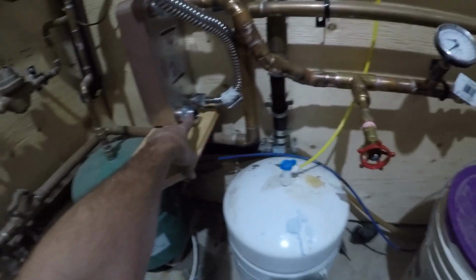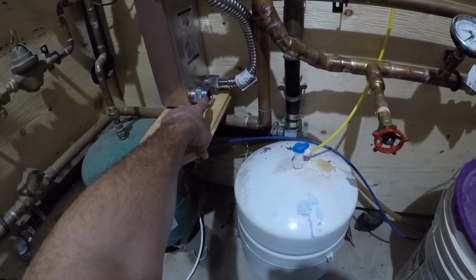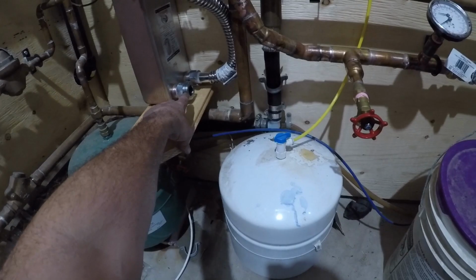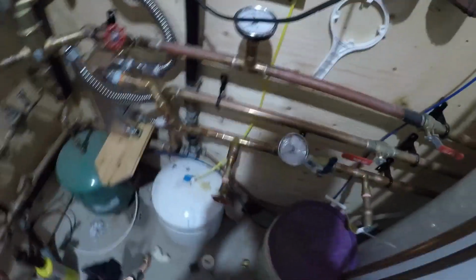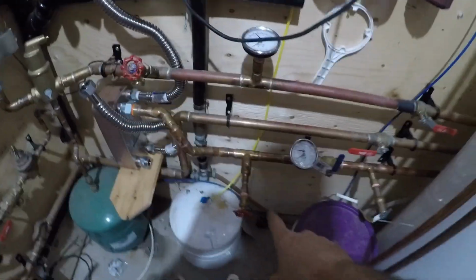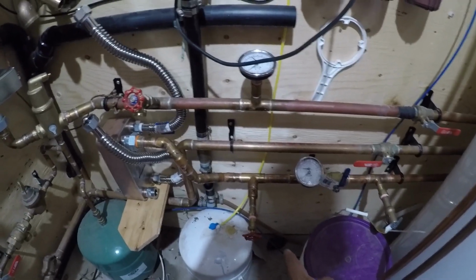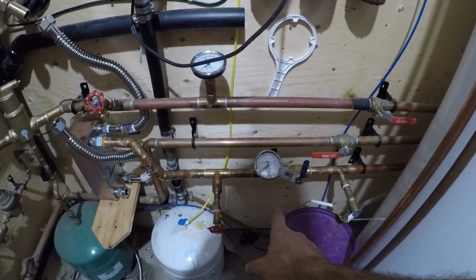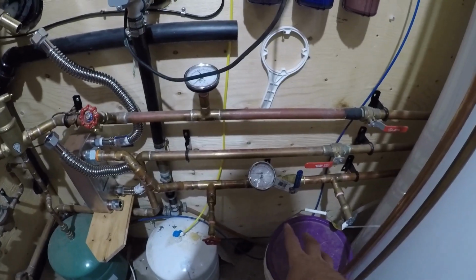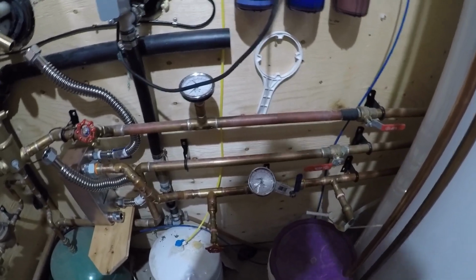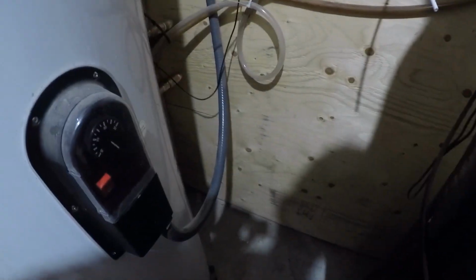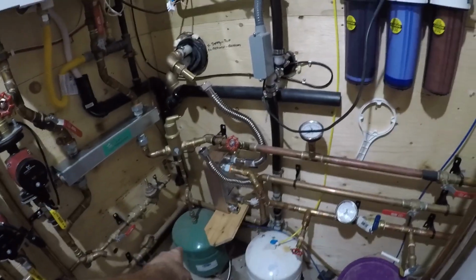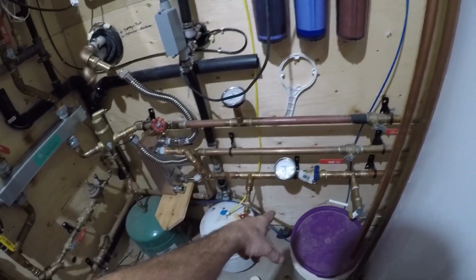So now I have to do the other side here. This one has a little bit less equipment in it, so it'll have, actually I guess it's about the same. It'll come off, it'll have another boiler drain on it to help purge. There will be the circulator pump and also an overflow tank. Unless I could put the overflow tank back there, might do that. Anyway, so there's not an overflow tank, an expansion tank, smaller than that one, just a little 2-gallon tank, and then the circulator pump will run back in over to here.